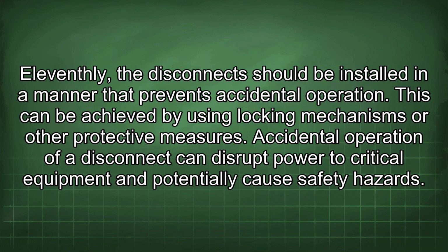Eleventhly, the disconnect should be installed in a manner that prevents accidental operation. This can be achieved by using locking mechanisms or other protective measures. Accidental operation of a disconnect can disrupt power to critical equipment and potentially cause safety hazards.